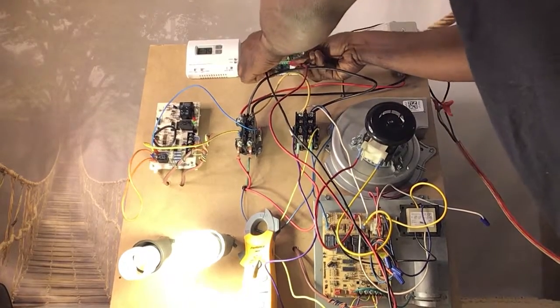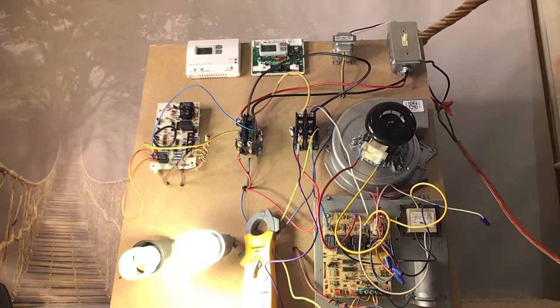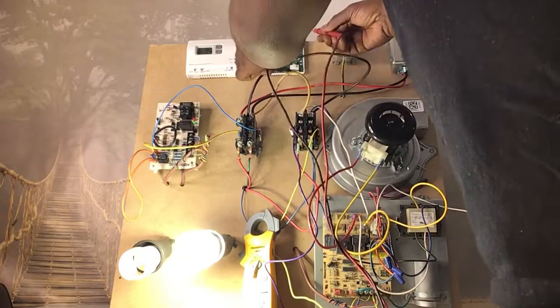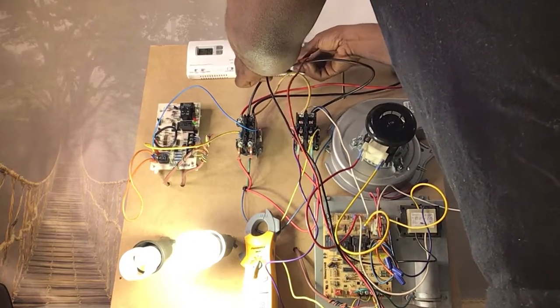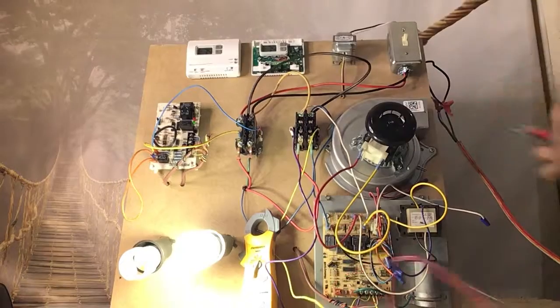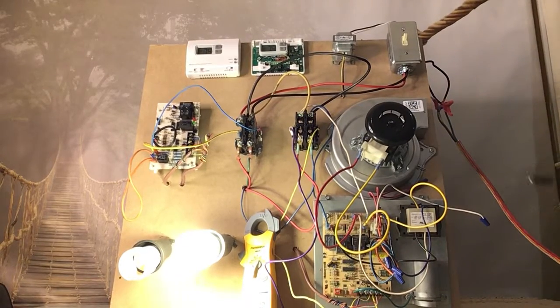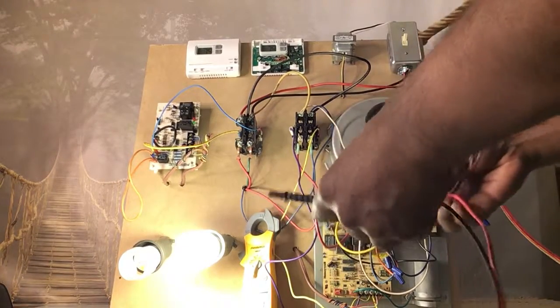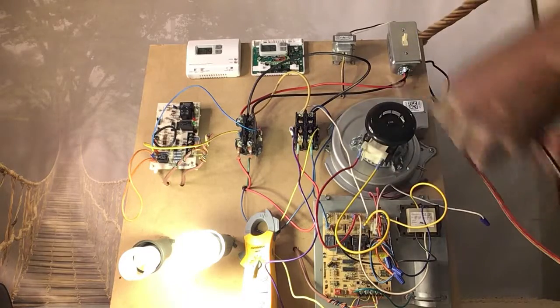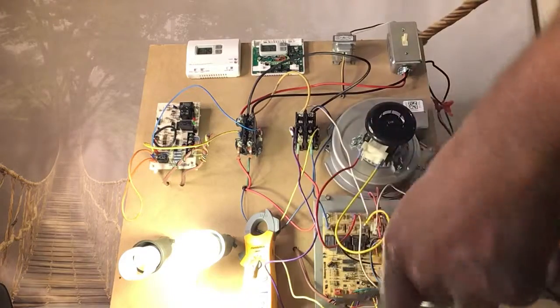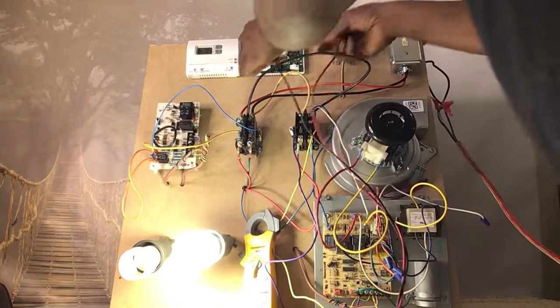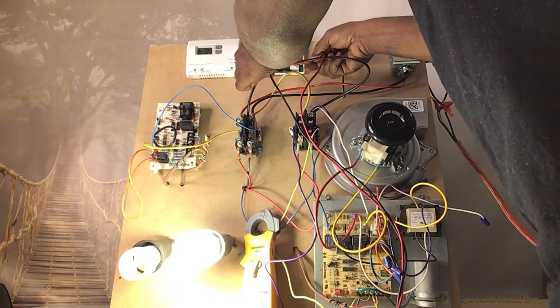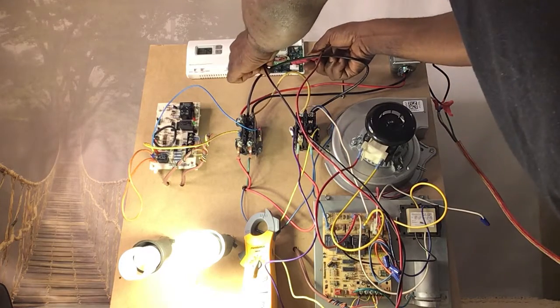So once you walk over to your thermostat and flip it on, if nothing happens and you got power from common to yellow at your thermostat, then you probably have a fault somewhere else. But the meter will help you to determine and dictate that. But you need to know how to use it. Volts AC, 24 volts. Common to yellow, 24 volts.